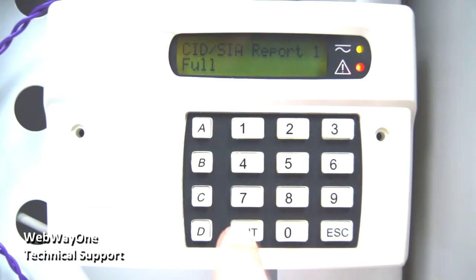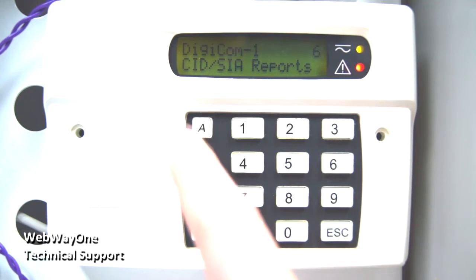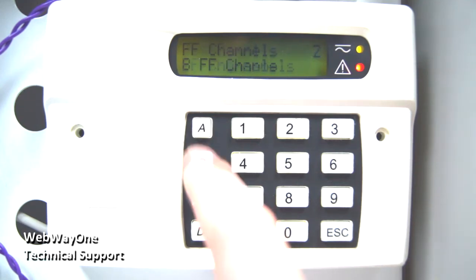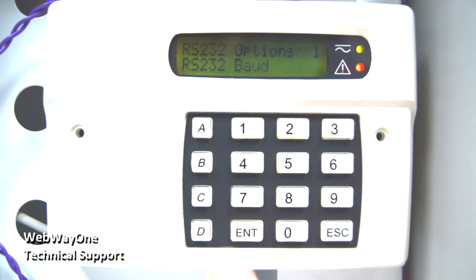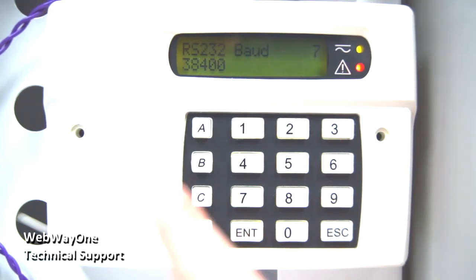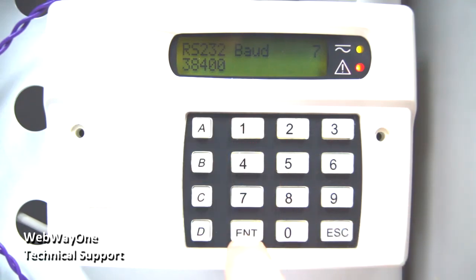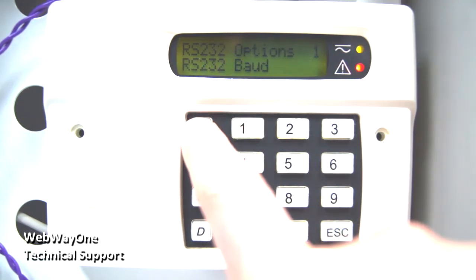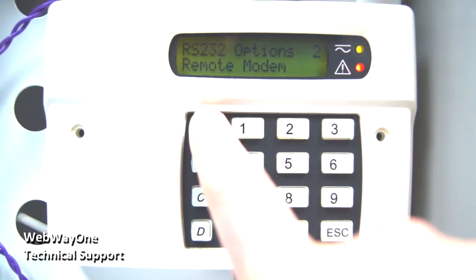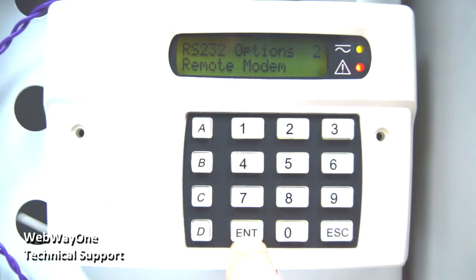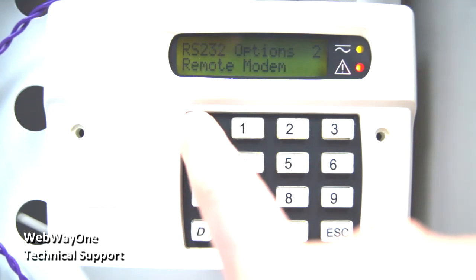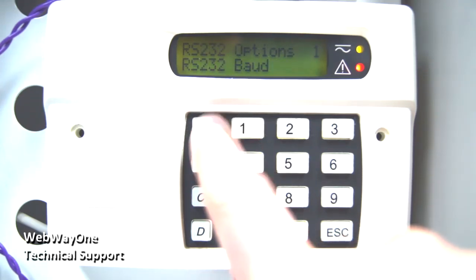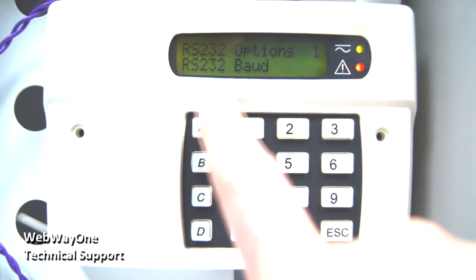CID/SIA reports should be set to full, and option 7 for FF channels should be set to 8 FF channels. The RS-232 options are found under menu 53. Set the RS-232 baud rate to be 38,400. Finally, set the option for remote modem to be enabled. Escape out of the menus and exit engineering. The configuration is completed and you should be ready to test alarms.